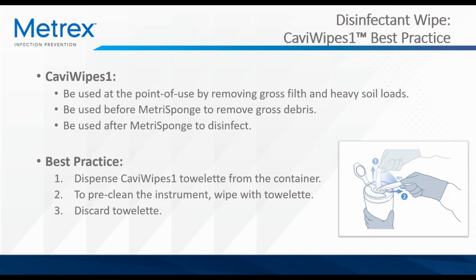Metrex product Cavi Wipes 1 is a disinfectant wipe that can be used at point of use to remove gross filth and heavy soil loads. You can remove gross debris with a Cavi Wipes 1 before further scrubbing and cleaning with MetriSponge. Or you can use Cavi Wipes 1 to disinfect a device that has already been pre-cleaned with MetriSponge. Again, the exact protocol will depend on the medical device manufacturer. Wipes are very easy to use. Best practice when using Cavi Wipes 1 is to dispense the towelette from the canister, wipe the instrument, and discard the single-use towelette.